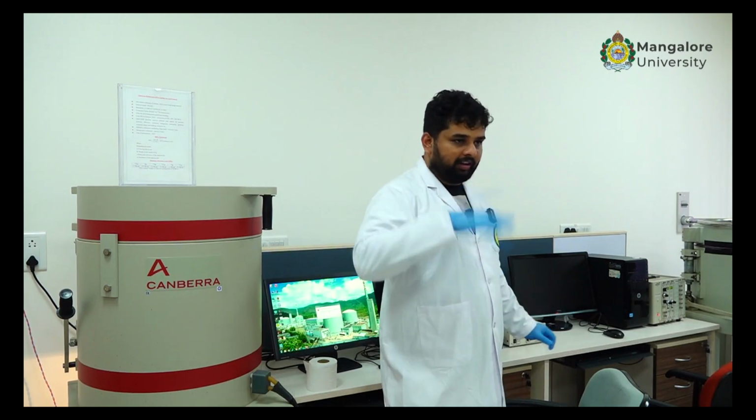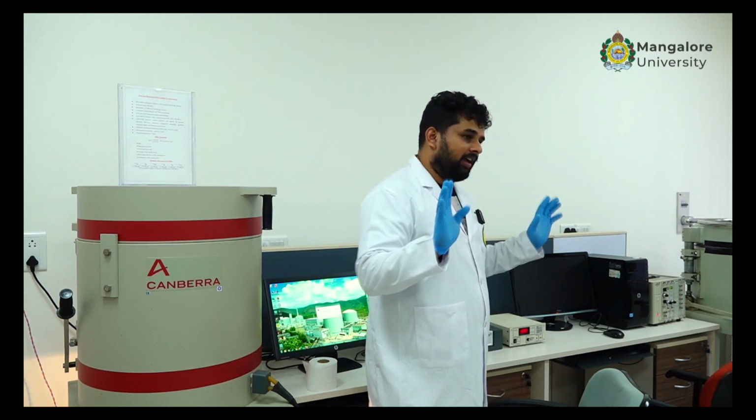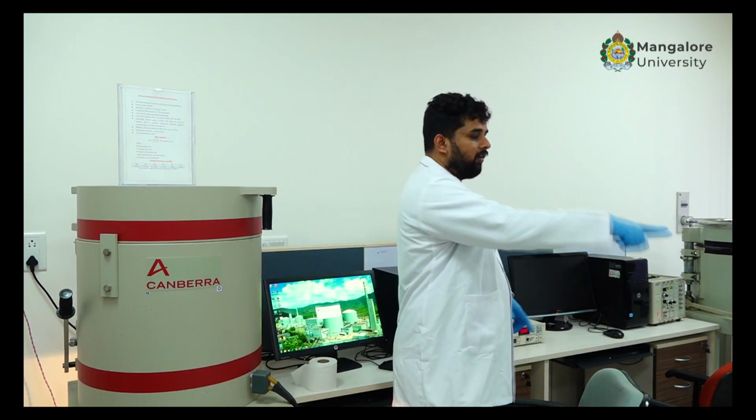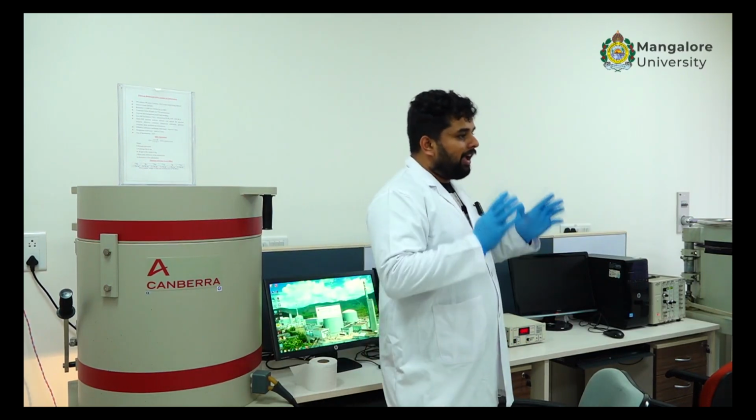I have explained already in the first class, high voltage is set, amplifier is set. We don't have to do anything afterwards. Now what I have to do first is calibration. What is the first calibration that we have to do? Open that sheet of paper. The first calibration that we have to do is energy calibration.